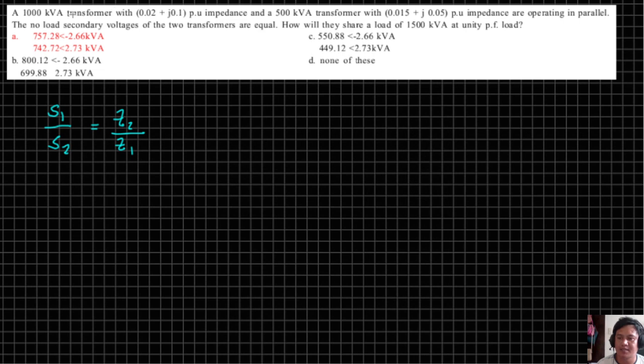Since it's written this way, this per unit impedance is based on its own kVA rating, and the other is based on its own kVA rating too. Let's have Z1 as is: 0.02 plus j0.1 per unit. But for Z2, we need to transform it to the base of the first transformer so they share the same base.